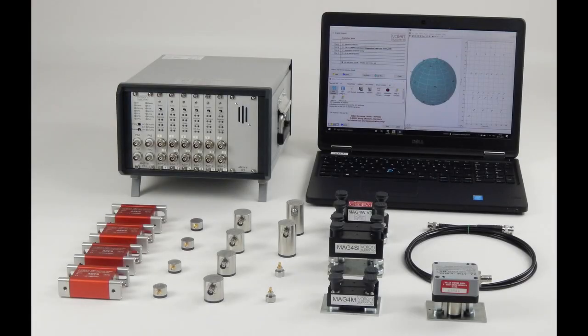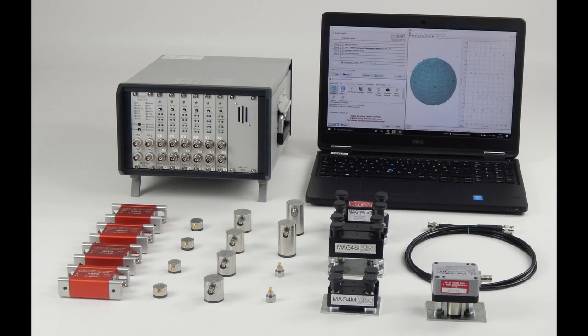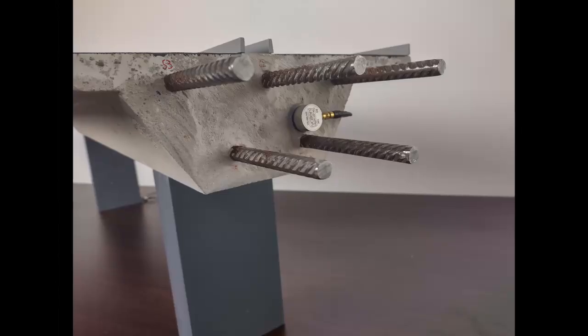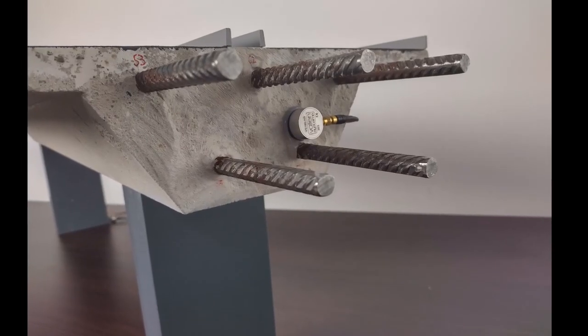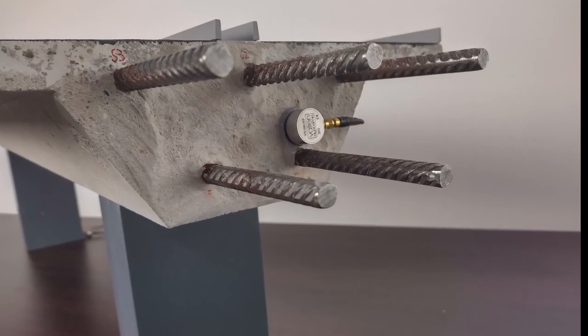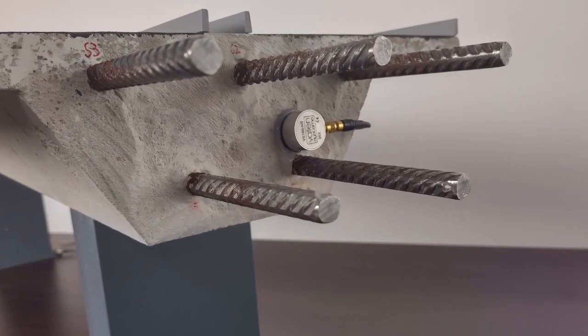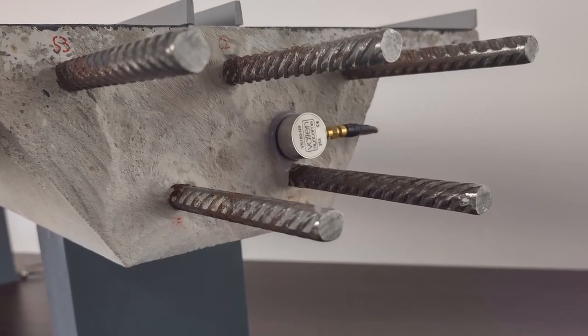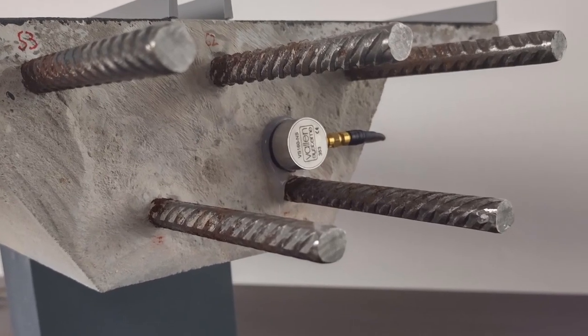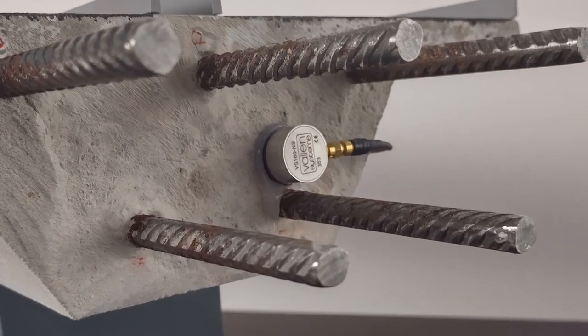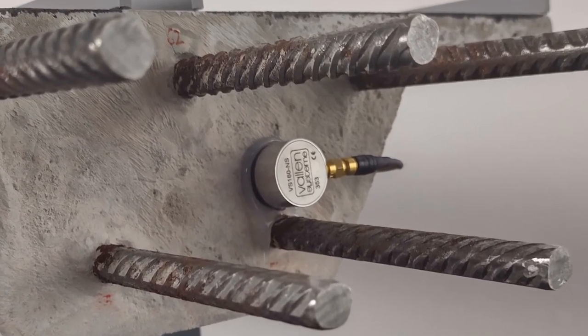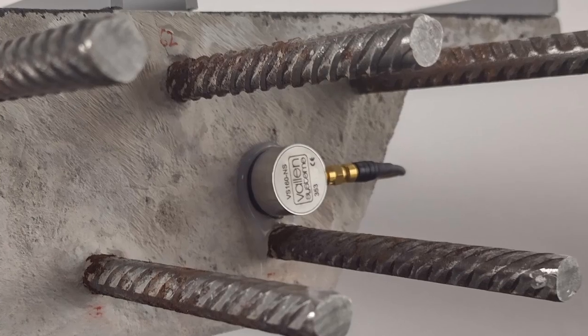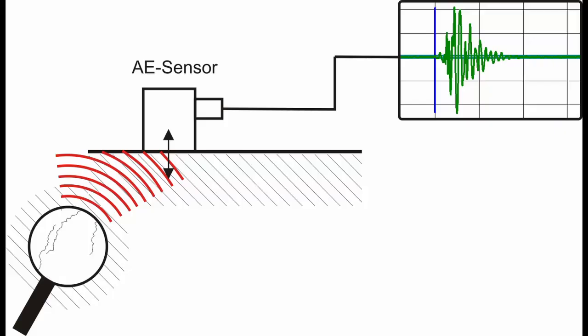An acoustic emission measurement system consists of sensors, a data acquisition system and a PC or laptop for storing and visualizing data. The sensors are brought into contact with the structure in a way that they are firmly attached to it. The monitoring task dictates where sensors are mounted.